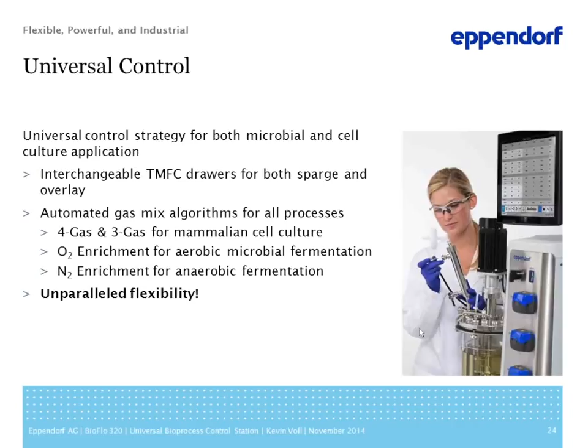We achieve this by offering interchangeable drawers. Instead of a very difficult and cumbersome change out of a thermal mass flow controller, the user, not a service rep, has the ability to remove a thermal mass flow control drawer, which includes all the control parts necessary for sparge gas, including mixing and flow, and insert a new drawer. This offers our customers and operators the ability to achieve high flow with a single TMFC for very basic microbial fermentation processes.